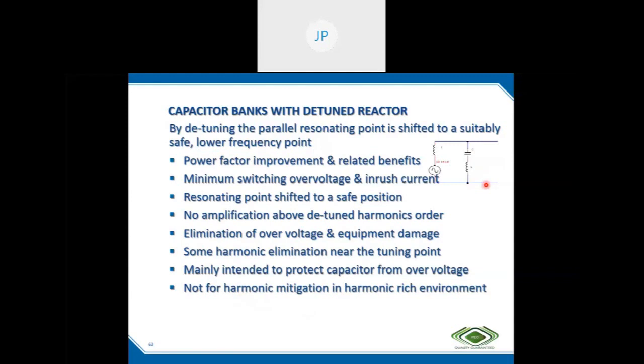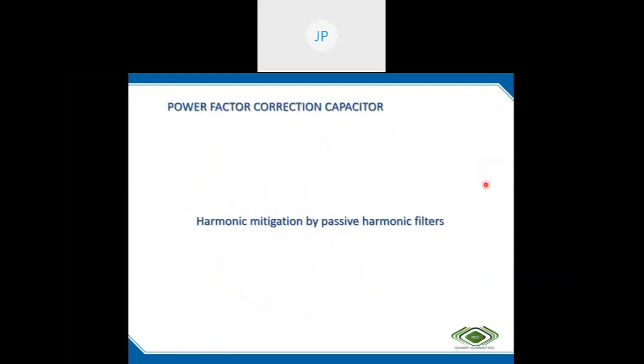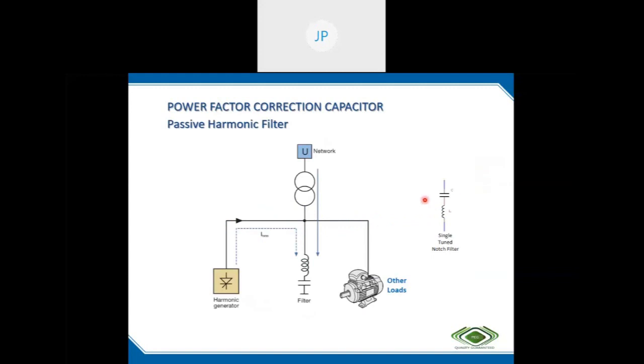The solutions are another. If we need to use power factor correction solutions in a harmonic rich environment to mitigate harmonics, we need filters. One type of filter is the passive filter. A passive filter is nothing but the same, but it is tuned at the filtering frequency, in our case the fifth order. The other one is not tuned to the fifth harmonic. If we tune to the fifth harmonic, the current rating and voltage rating will be different, because it has to handle the harmonic voltage and the harmonic current.